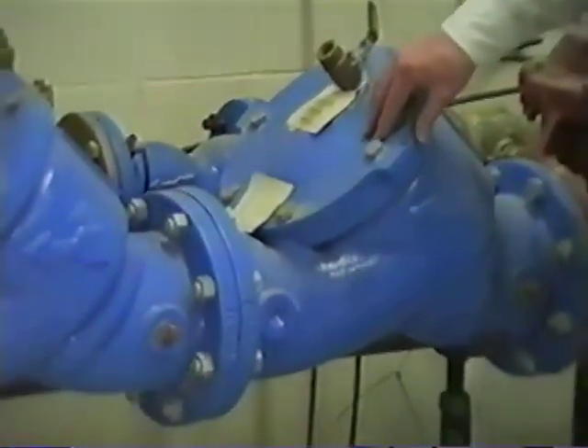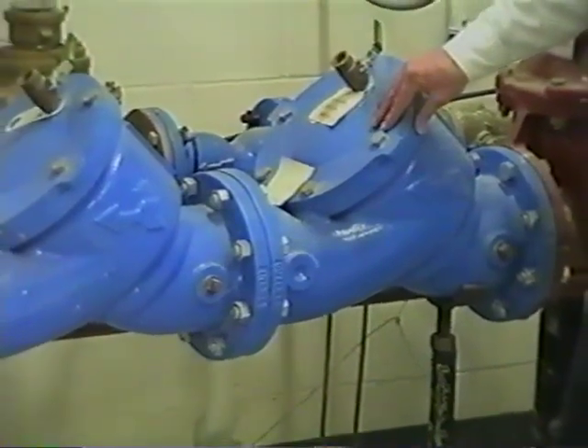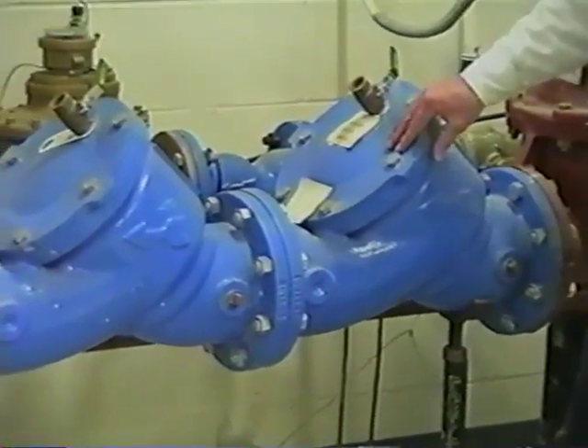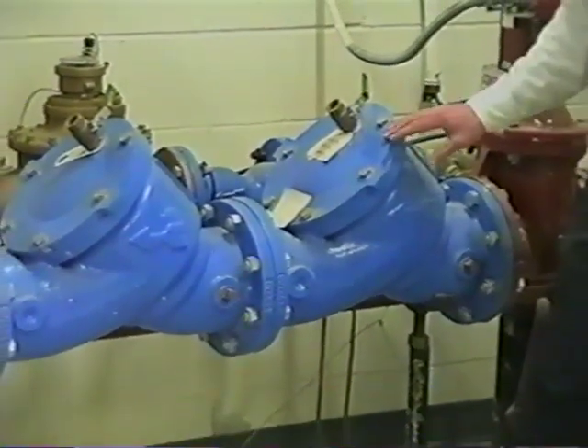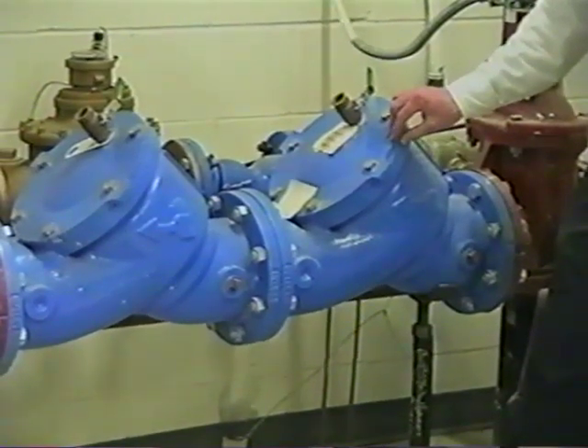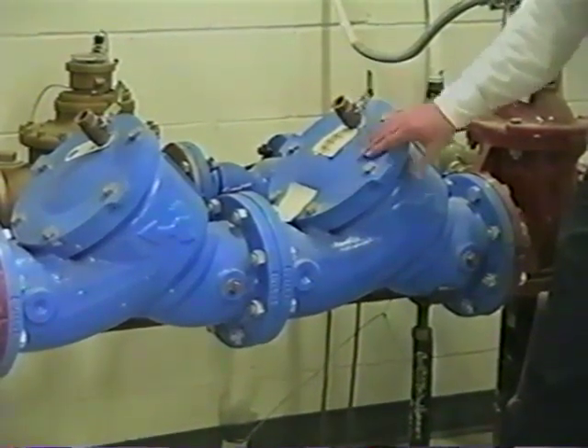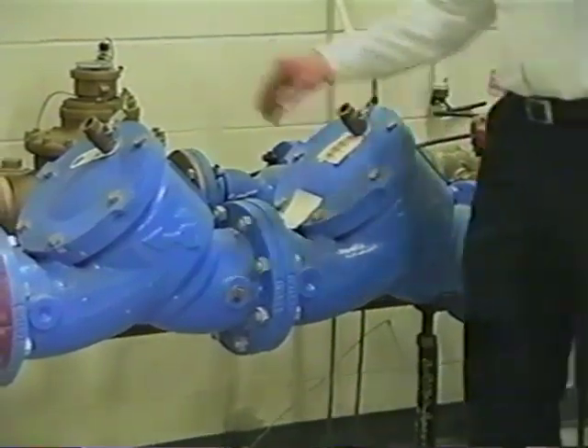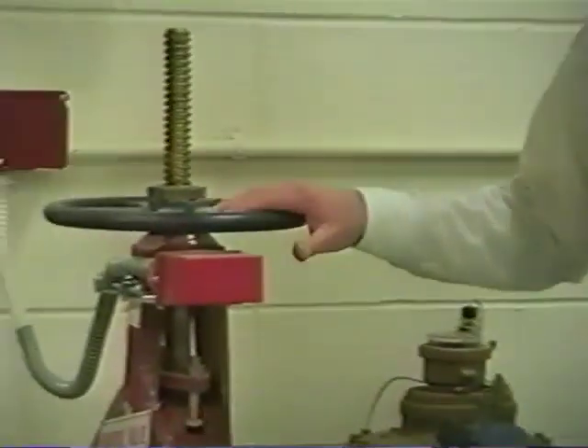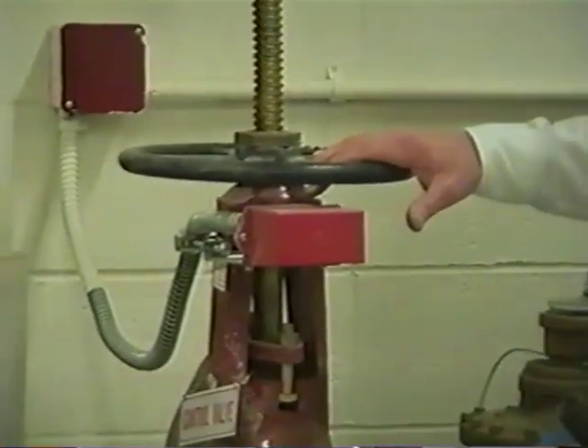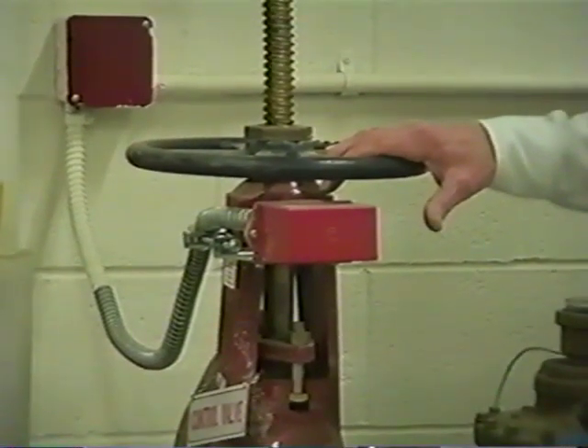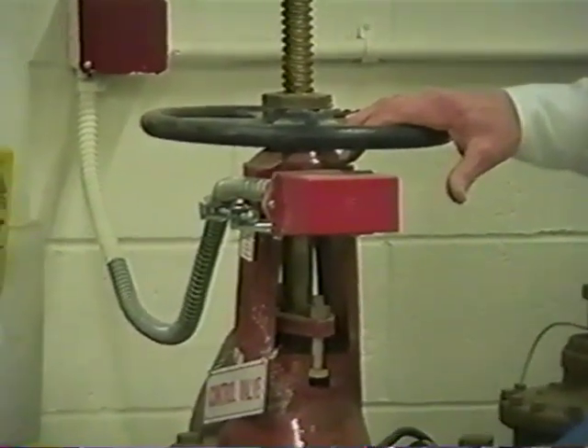Next is a backflow preventer. This prevents water from the sprinkler system seeping back through the pipes going into the domestic water, which we would be drinking. So this is a backflow preventer. Next in line would be another OS&Y shutoff valve that the fire department would use to shut down the sprinkler flow.